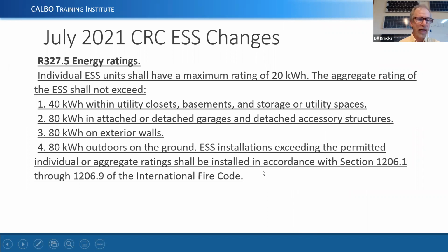Now, there is a series of energy ratings that tells us what the maximum size that can go in any one place. And so the aggregate rating that could go inside of the dwelling unit, which would include utility closets, basements, and storage or utility spaces, would be 40 kilowatt hours. In attached garages or detached accessory structures, we can go up to 80 kilowatt hours. On the exterior wall of the building, we could go up to 80 kilowatt hours. And outdoors on the ground, in a ground-mounted installation, you could put 80 kilowatt hours. And the State Fire Marshal's Office about 3 months ago issued a bulletin that says that you can go up to all 4 of these items. So you could actually install 280 kilowatt hours of energy storage on a home.